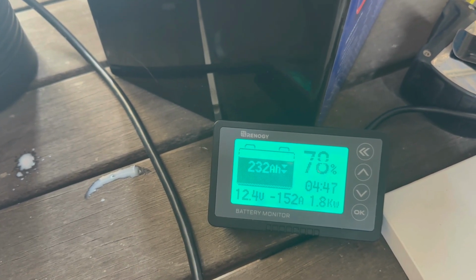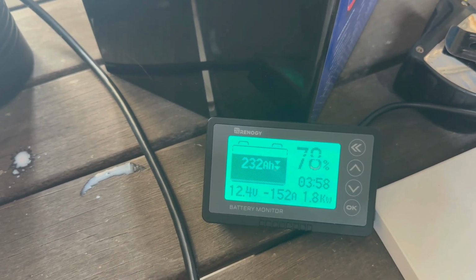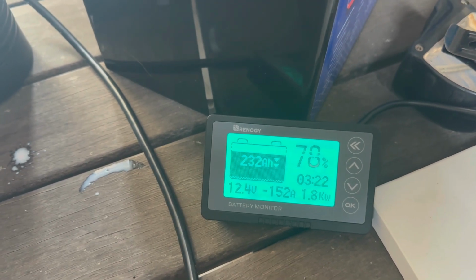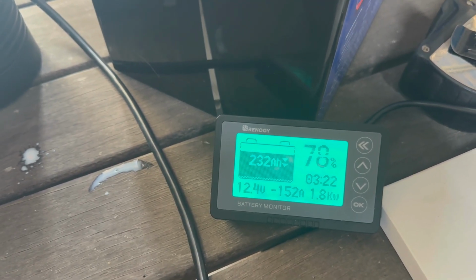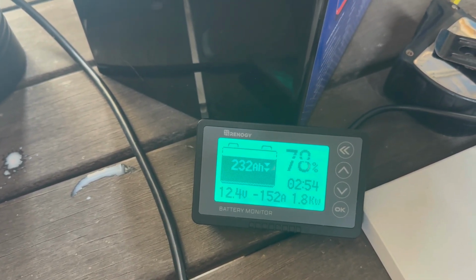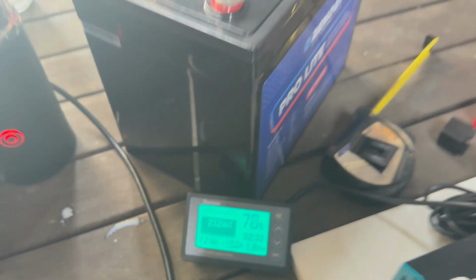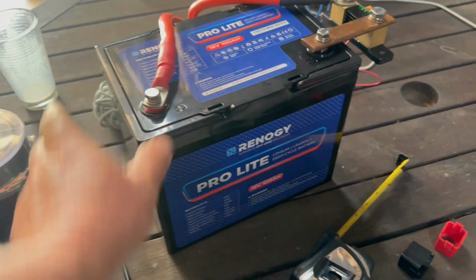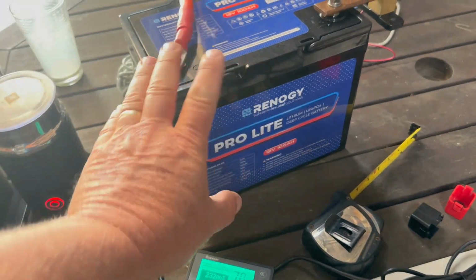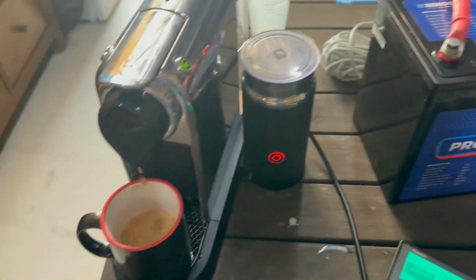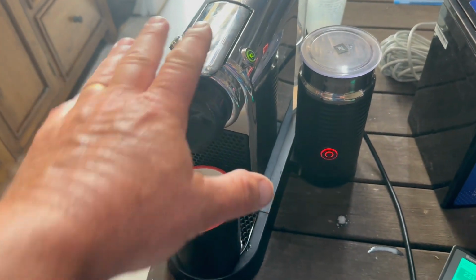The load's coming off and on. The maximum I've seen is 1.8, 152 amps. Now you're not going to do that on a 100 amp hour battery, guys, on a 100 amp BMS, so that's not going to work. You can't use the 2000 watt inverter with that battery running a typical coffee machine or pod coffee machine.